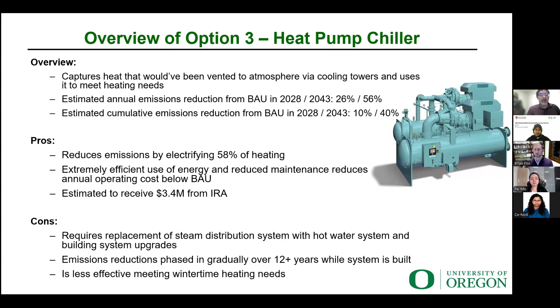The pros are that it reduces emissions by electrifying some 58% of heating, a very efficient use of electricity. The cons: it requires replacement of the steam distribution system with hot water. When you pull heat out of buildings to cool them, you can repurpose that heat only as low-grade warm water, around 135 to 170 degrees Fahrenheit. You can't get it all the way up to steam temperatures, so we'd have to dig an entirely new set of pipes to put those hot water lines in.